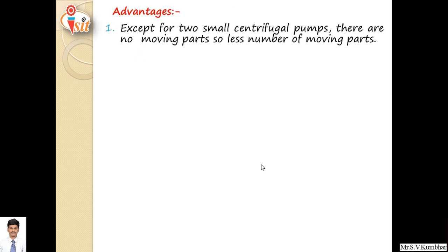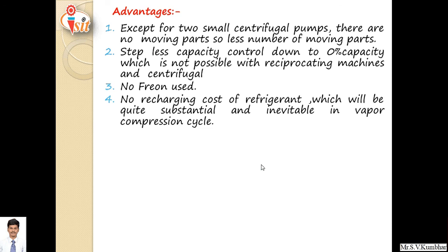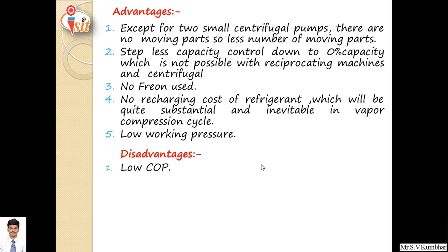Advantages of lithium bromide water absorption system: except for a small centrifugal pump, there are no moving parts. Stepless capacity control down to 0% capacity, which is not possible with reciprocating or centrifugal machines. No Freon gas is used. No recharging cost of refrigerant, which would be quite substantial and inevitable in vapor compression cycle. Low working pressure, which is the biggest advantage of this system.